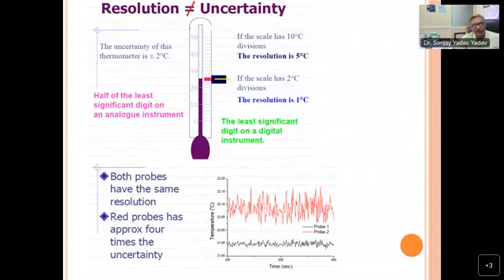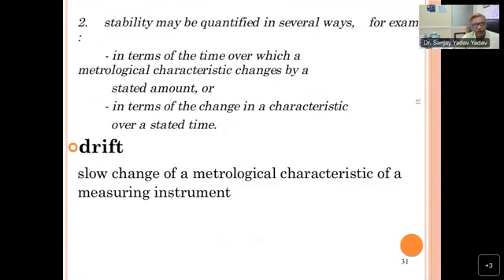Then uncertainty is never resolution. So please understand, uncertainty and resolution are different quantities. In a particular example, you can say resolution is 5 degrees centigrade here, and in another example the resolution is 1 degree centigrade, but uncertainty you can see by the scattering of the results. Drift I have already explained, unilateral and multilateral direction. You can have a drift definition.